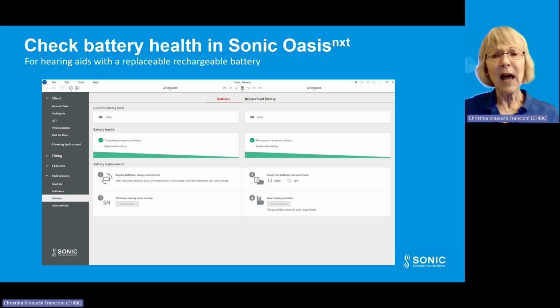For hearing aids that do allow changing the battery in the clinic, the battery replacement steps will be visible in the fitting software. If indicated, replace the battery. When doing so, enter the serial number of the battery in step 3. This needs to be done for traceability in case of a recall situation and for warranty in case of a defect battery. Furthermore, the battery statistics need to be reset to ensure a correct battery level readout, which you can do with step number 4.